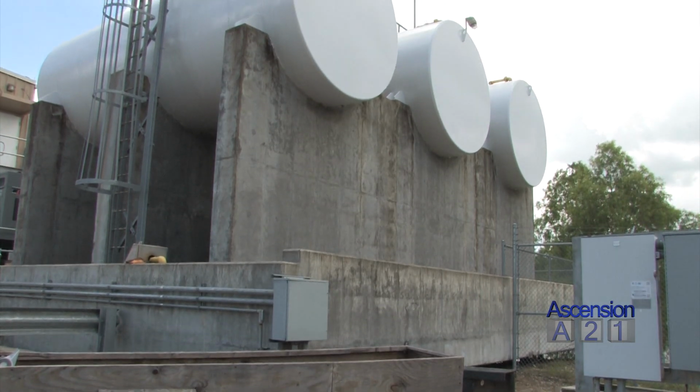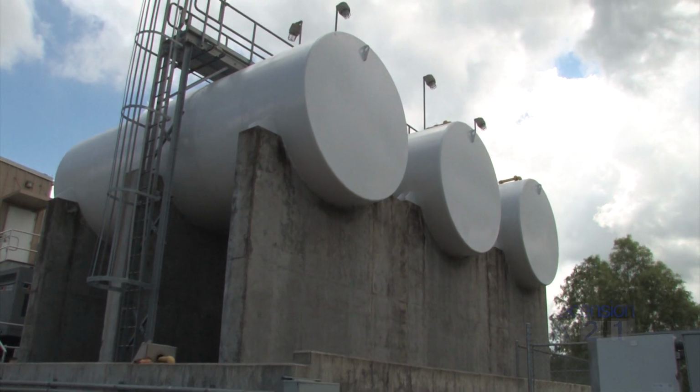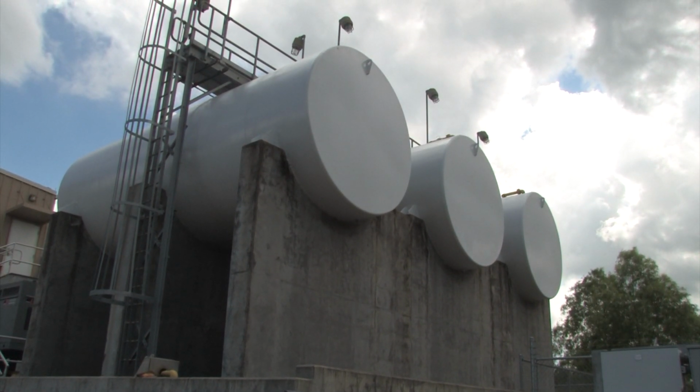Fuel-wise, just to give you an idea, each pump burns 66 gallons an hour. When they say crank up, that's what you're looking at, plus a 5-man, 6-man crew. If 5 pumps are running, it's 10,000 gallons that I will be ordering every 24 hours.